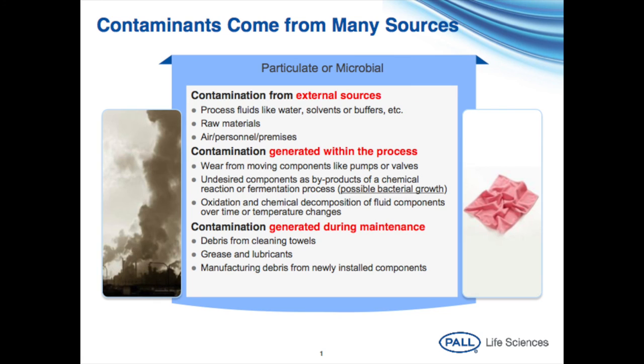Cleanliness is a key component of our strategy. The microfluidizer and processing pathways, like tubing and hold vessels, must be clean and contaminant-free. In our early work with the squalene nanoemulsion, we learned that even a cleaned laboratory microfluidizer can generate a solution with a bacterial load if that cleaning is not robust and filtration directly out of the unit was not employed.